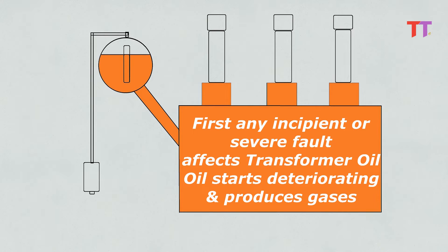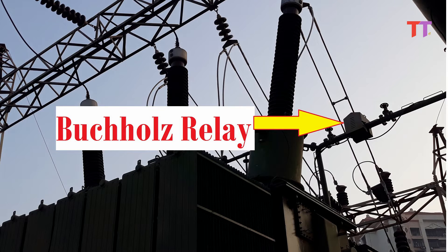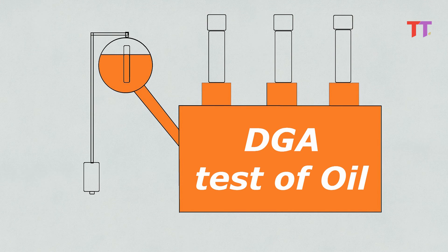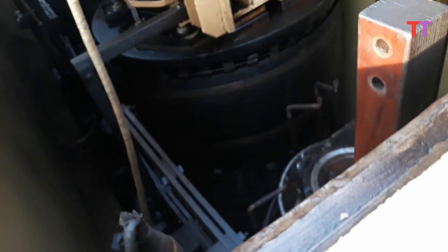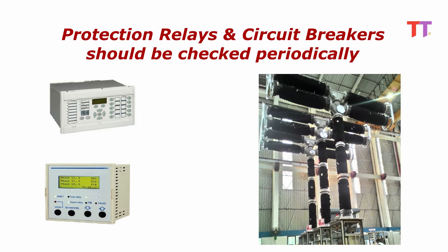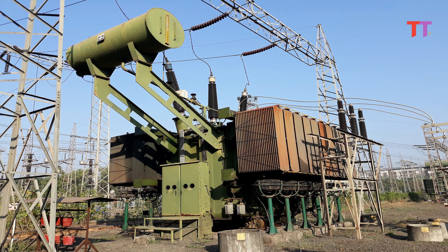Any incipient or severe fault affects transformer oil — oil starts deteriorating and produces gases. These gases trigger Buchholz relay or can be identified during DGA test of oil. If any gases are identified indicating a fault, then immediately transformer internal inspection should be done — windings, leads and core should be checked for any insulation damage or any other fault. Protection relays and circuit breaker should be checked periodically so that they function efficiently during fault and isolate the faulty portion effectively. This effective fault isolation avoids excessive stresses on the power transformer, preventing it from possible explosion.